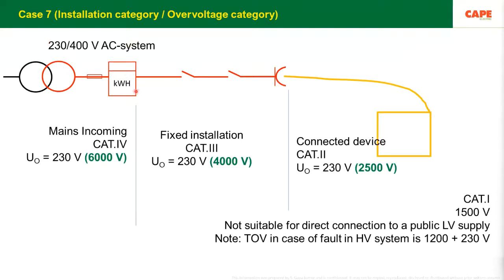Case number 7. Installation category or overvoltage category. Here, you must understand that any failure in the insulation of a conductor or an apparatus will create a problem, or it can create an accident. In our electrical installation, starting from the transformer up to the meter board, you have very strong electrical devices with very big insulation. Then at the fixed part of the installation, you have devices with lesser insulation, and your connected devices have even lesser insulation. So there are installation categories, impulse voltages, and so on.